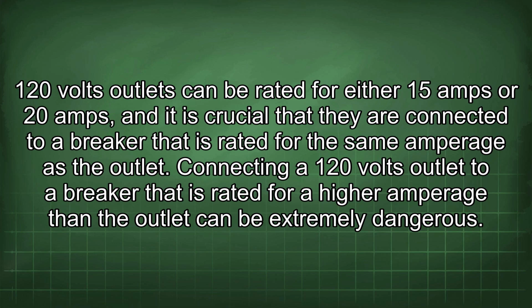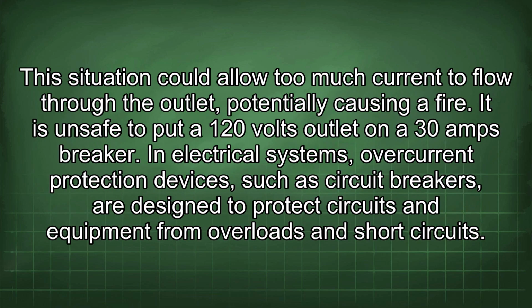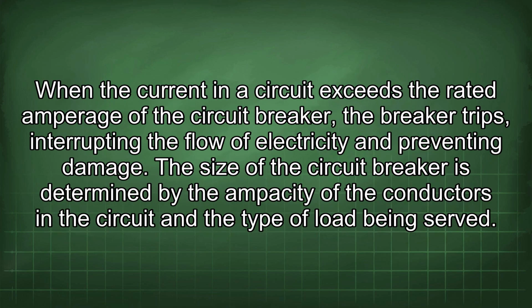Connecting a 120 volt outlet to a breaker that is rated for a higher amperage than the outlet can be extremely dangerous. This situation could allow too much current to flow through the outlet, potentially causing a fire. It is unsafe to put a 120 volt outlet on a 30 amp breaker. In electrical systems, overcurrent protection devices, such as circuit breakers, are designed to protect circuits and equipment from overloads and short circuits. When the current in a circuit exceeds the rated amperage of the circuit breaker, the breaker trips, interrupting the flow of electricity and preventing damage.